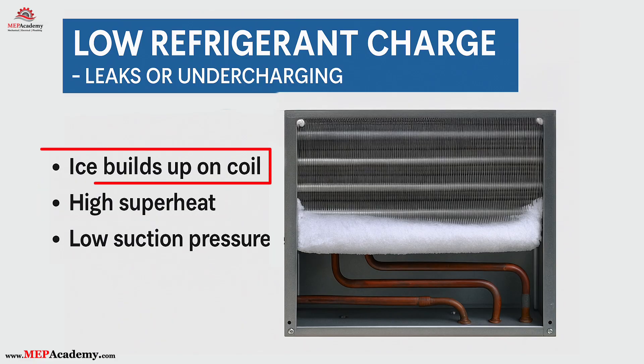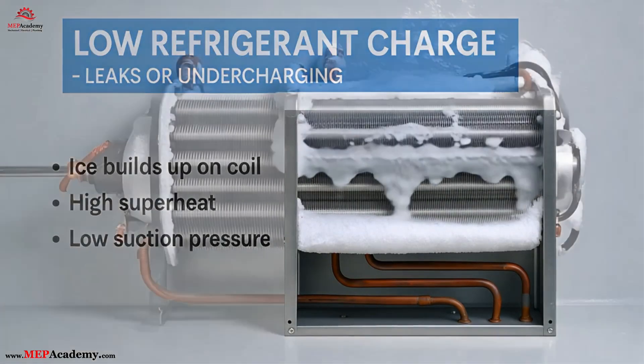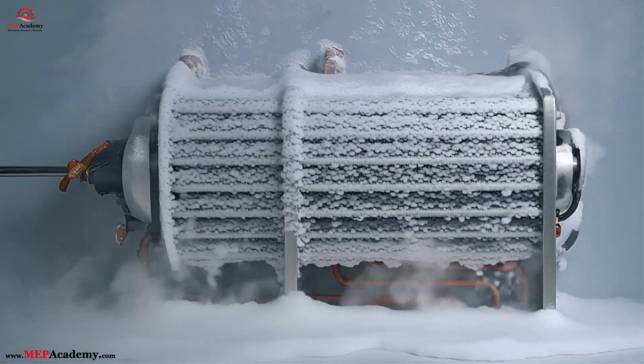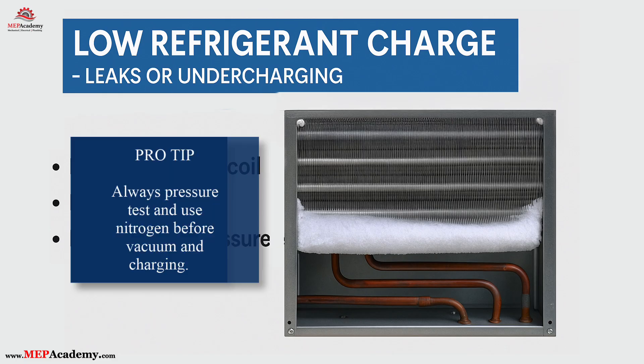Ice buildup on the evaporator. Ice builds up on a coil with low refrigerant charge because the reduced pressure lowers the refrigerant's boiling point, causing the coil temperature to drop below freezing and moisture in the air to freeze on the surface. Pro tip: always pressure test and use nitrogen before vacuum and charging.